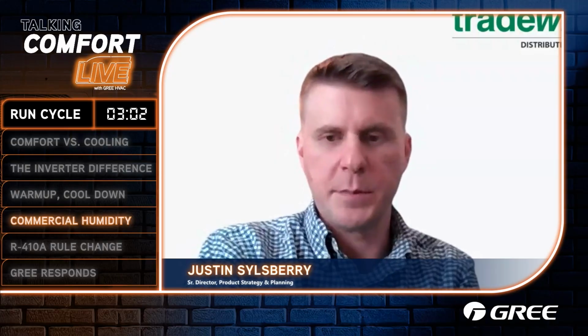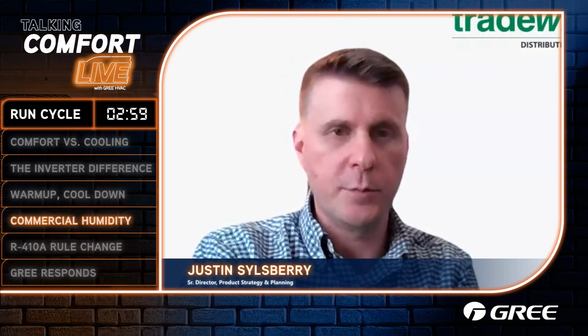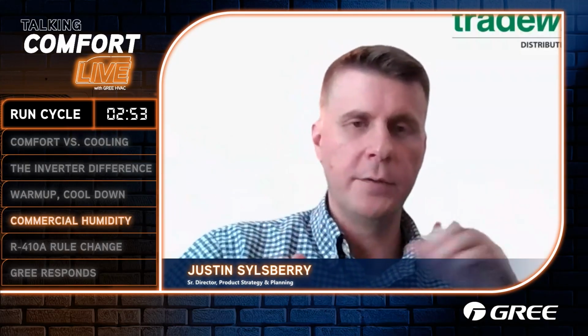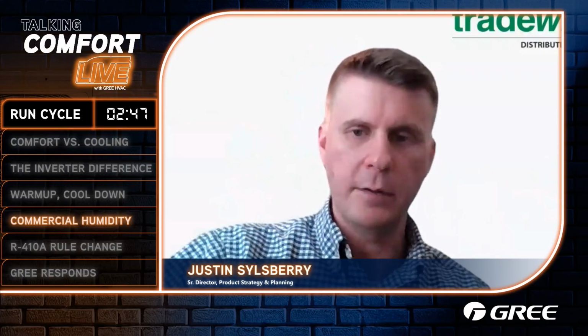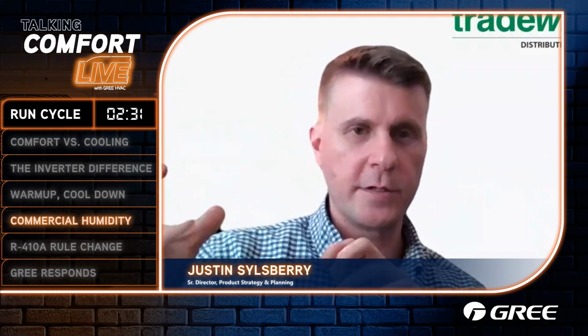One of my favorite ways to deal with that is to take a VRF system. What's great about a VRF system is it's multi-zone and variable speed, variable capacity. It can shift refrigerant load around a building to where you need that capacity. So in the morning, if everybody's in that conference room, the VRF system can send refrigerant, it can send capacity to that conference room to keep it nice and cool. And then when they leave and go to their cubicles after the morning meeting, it'll take that capacity, that refrigerant, and shift it over to the other side of the building where all the cubicles are.